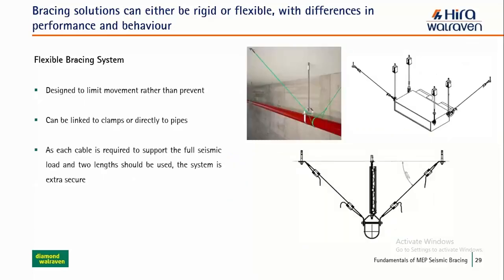Then we have the flexible bracing system, which has its own advantages. The idea is the same, to limit movement rather than prevent it, and it's very easy to install. It can be linked directly with the clamp or directly with the pipe, so no extra accessories are required. Each support requires two cables with equal spacing, and these cables have different load carrying capacities to control seismic forces based on load requirements.